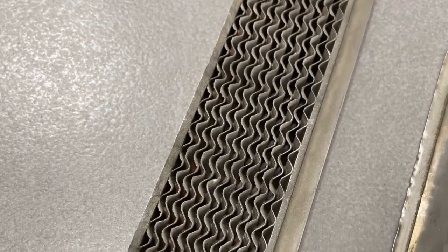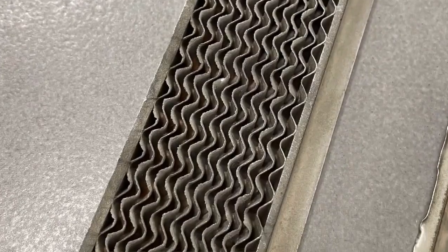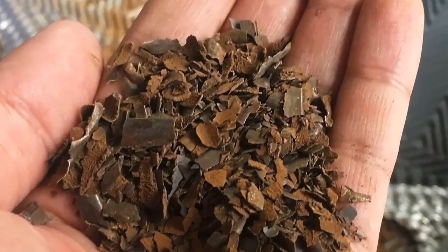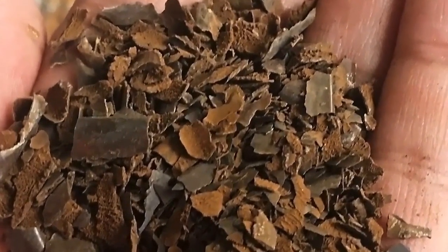These detergent fluids can remove deposits of limestone, dirt, or fats that have accumulated inside the exchanger. Obviously, the heat exchanger must still allow a decent flow of fluid. If it is completely clogged, it will no longer be possible to clean it because the fluid will not pass through, or at least preferential channels will form where the cleaning fluid passes through but does not clean the entire bundle, which will nullify our efforts.